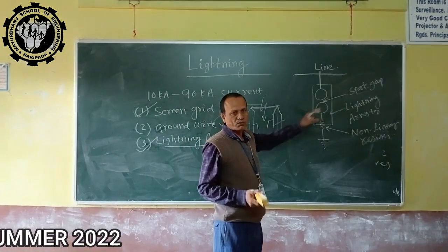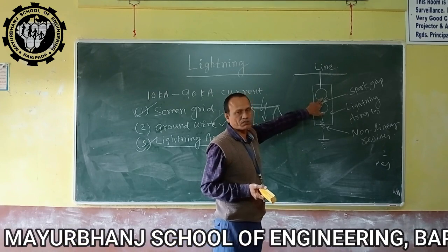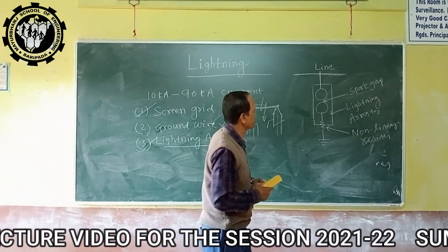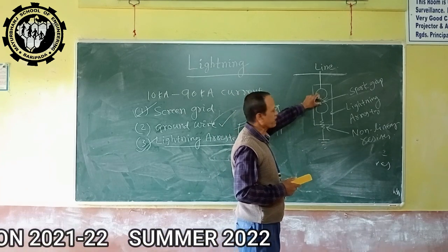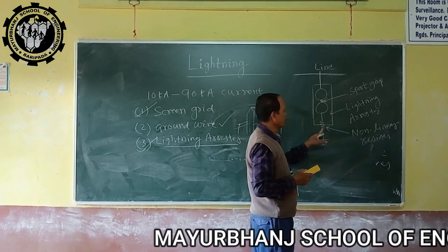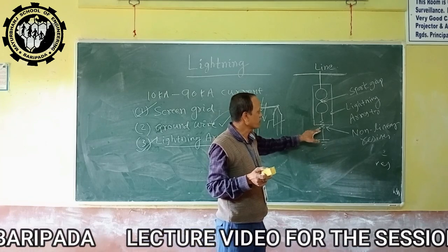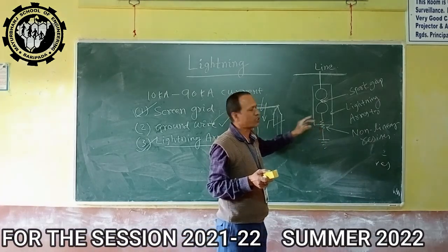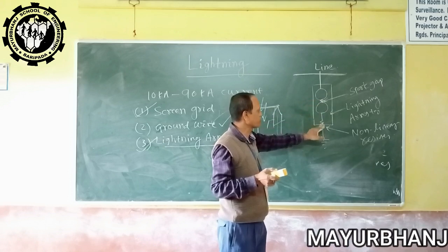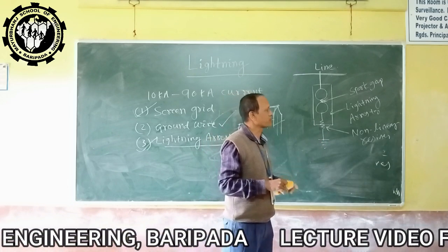Under normal conditions, when normal current flows and there is no over voltage, there is no spark between the two electrodes of the lightning arrester. But when there is sudden lightning or some over voltage in the system, an arc develops across the spark gap and passes to the non-linear resistor. The non-linear resistor's resistance becomes lower when over voltage takes place, but under normal condition its resistance is high. So the over voltage passes through this low resistance to the earth. In this way, it protects the equipment.